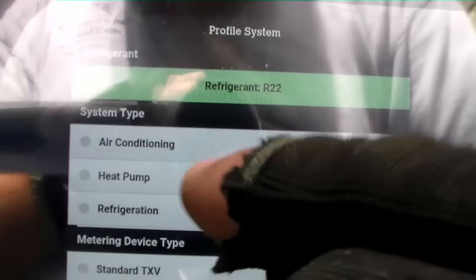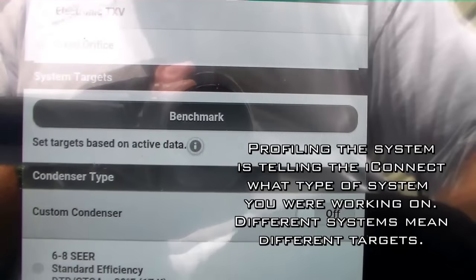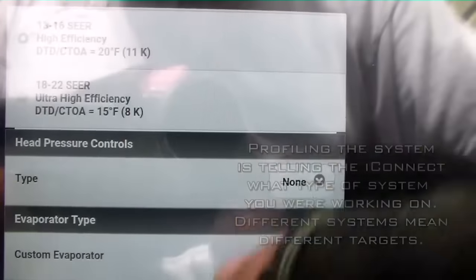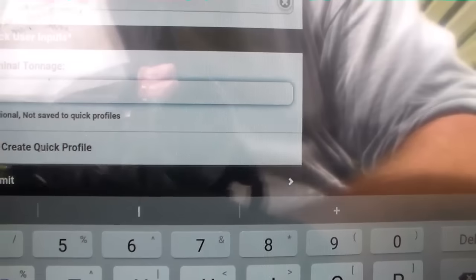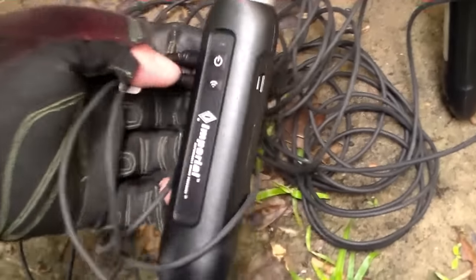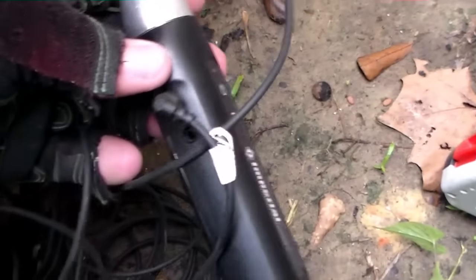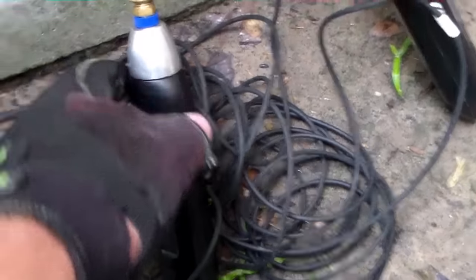We're profiling the system now — heat pump, cooling, standard TXV, 13 SEER system, standard evaporator, 2.5 tons. As you can see we have our probes on. Low side adapter probe: the first one is for superheat and goes on the suction line. The second one is for ambient temperature, dangling up here. We have our high side probe and one more probe for liquid line temperature so we can get subcooling. All those are put in, ready to go, all turned on.